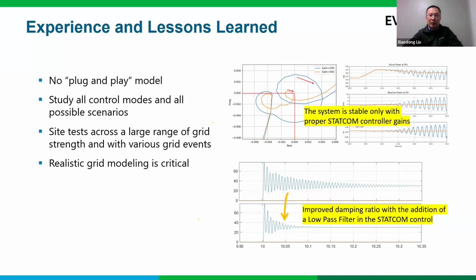One lesson learned from the STATCOM project is that the STATCOM has different operation modes, and all operation modes might need to be studied at different grid strengths, grid contingencies, farm internal contingencies, and different farm outputs. For example, the diagram below shows the STATCOM's response on the grid event in the reactive power control mode. That's the one control mode we overlooked. The STATCOM does dampen the high frequency oscillations, and you can see the oscillations going down. But it's not good enough to meet the performance requirement of at least 30% damping ratio for any oscillations. So this scenario was unfortunately overlooked in previous studies.